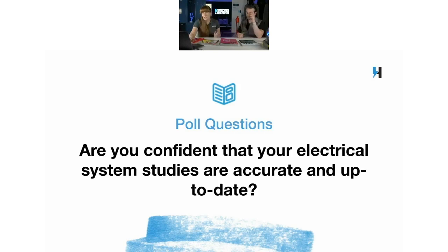John says it sounds like he may need to add an annual utility company fault current chart to his electrical safety manual. That's actually not a bad idea, checking in more frequently just to make sure nothing's changed too much. That's something the NFPA 70E recommends for generation and transmission organizations, depending on where you are.